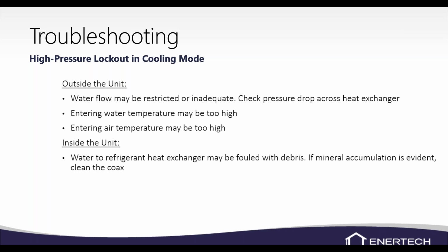Inside the unit, the water to refrigerant heat exchanger could be fouled with debris. That's normally what we'll see on an open loop system, so a pump and dump. If you've got a strainer on that water circuit, make sure that strainer is clear. And we have a calculation we can do to see if a heat exchanger has failed. And we don't have to just guess whether it's plugged up.